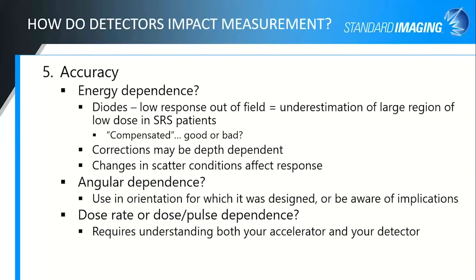Because of the energy dependence, you may have corrections that are different at different depths because of the attenuation of the beam through the water above. And of course, changes in scatter condition affect the response because the scatter energies are a little broader spectrum usually than the beam itself. You can have angular dependence from your detectors. So the key there is to make sure you're using it in the orientation for which it was designed, or at least be aware of the implications of moving away from that orientation, the recommended orientation.